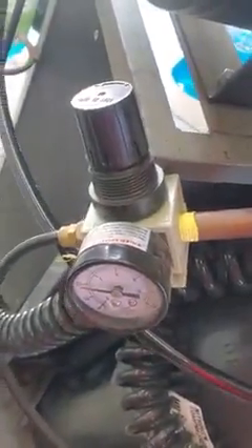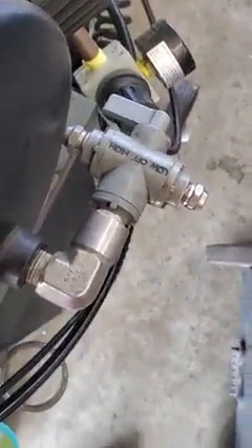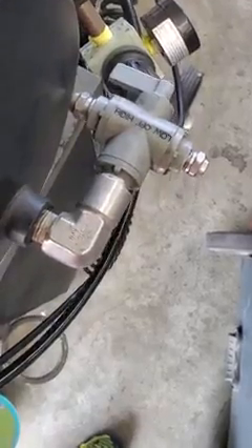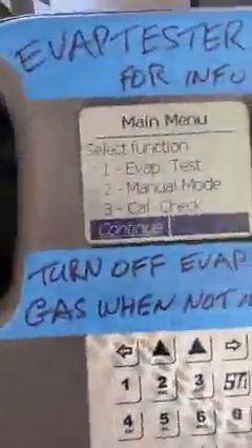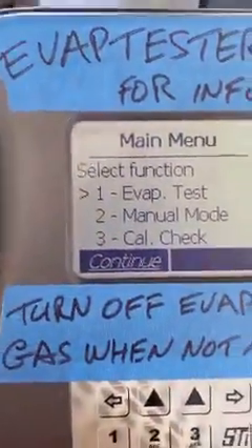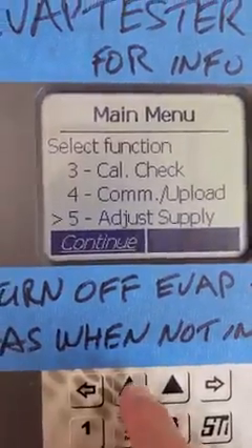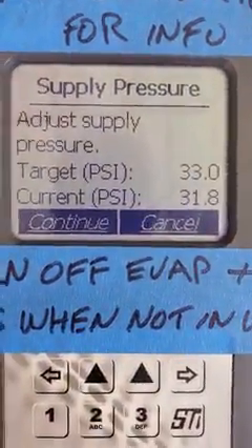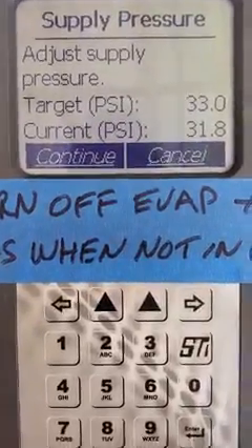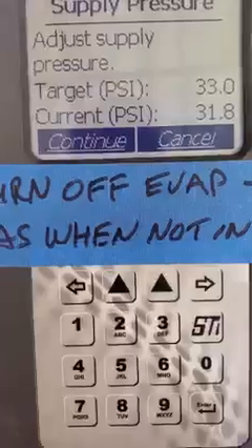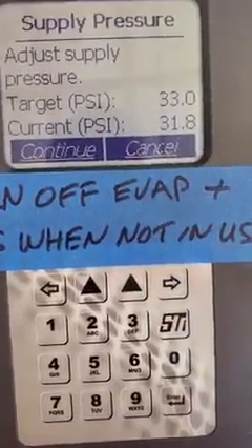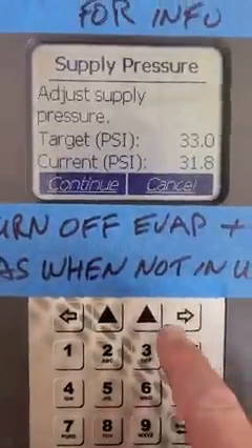And then you have a second, more precise regulator that you will use to set the pressure in your machine to 32. The calibration valve is set on high so the calibration tank can breathe. Now we'll check a few things on the machine first. So push 5, continue, and it'll show you the actual pressure in the machine, which as you can see is 31.8, which is perfect. 32 is what we recommend, but anywhere from 31 to 33, the machine will work perfectly.